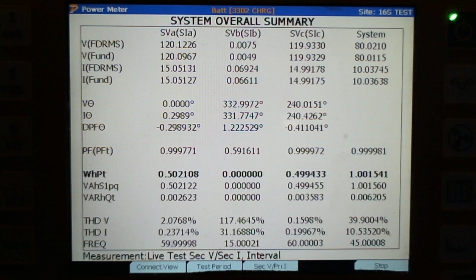You can hit F3, interval, and then test period. That'll help you with the demand testing you're talking about. You can let it run for 15 minutes and it will accumulate kW during that period of time. And then you want instantaneous so you can see it.